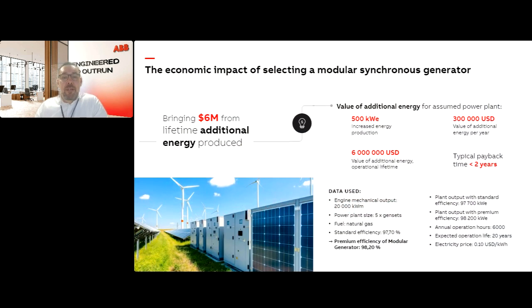So if we take, for example, a power plant with 20 megawatt engines, the power plant size of 5 gensets, so roughly 100 megawatts in total, natural gas as the fuel for the engines, and consider that the efficiency of a typical standard generator would be around 97.7%.